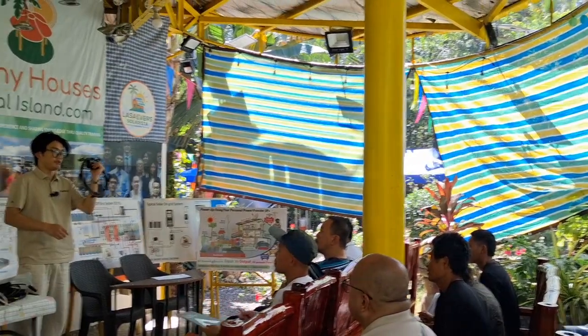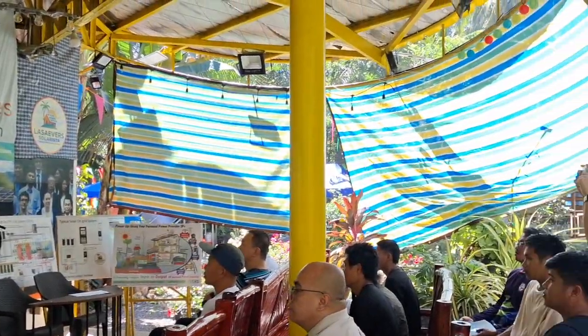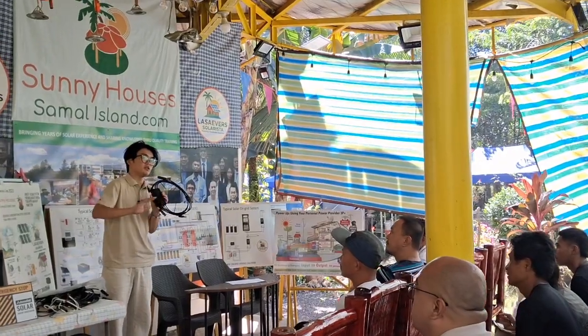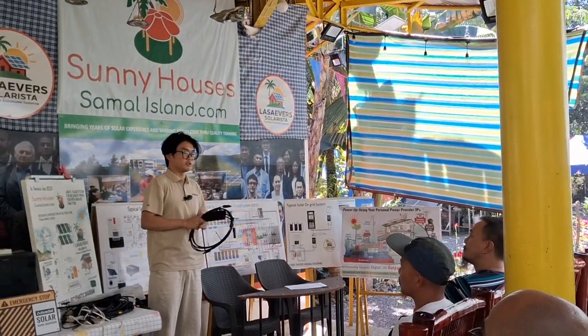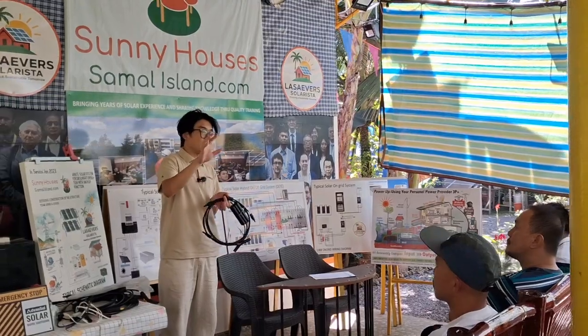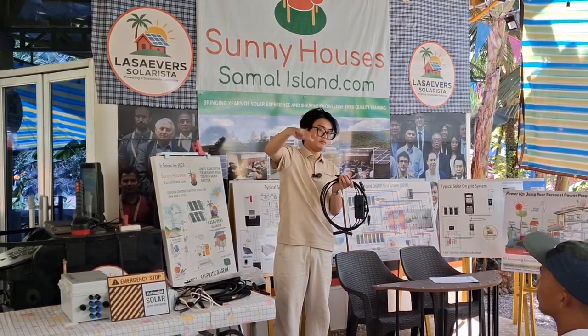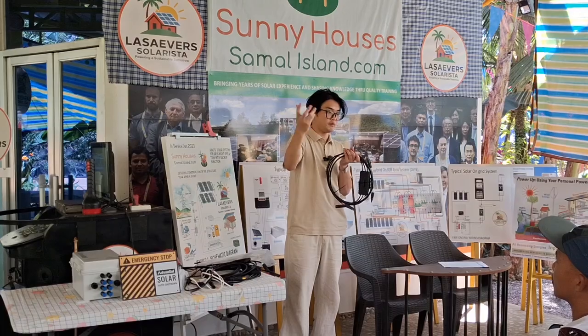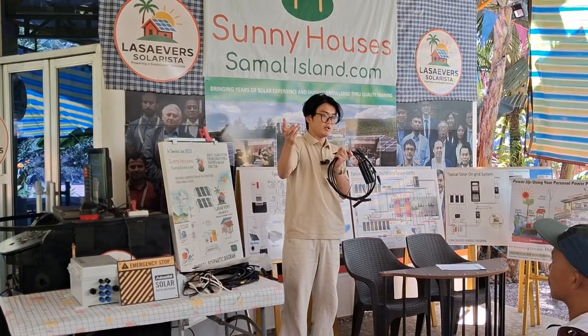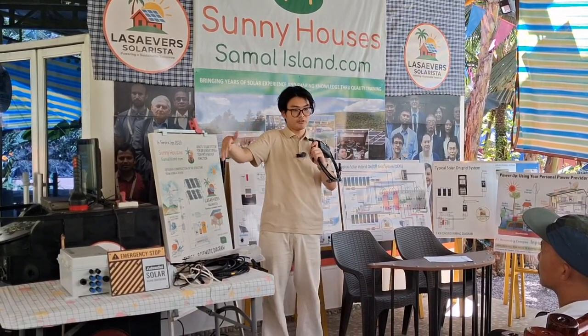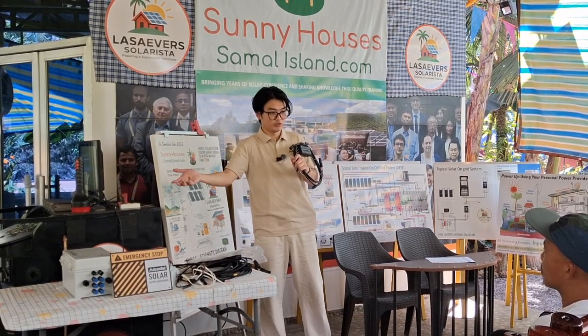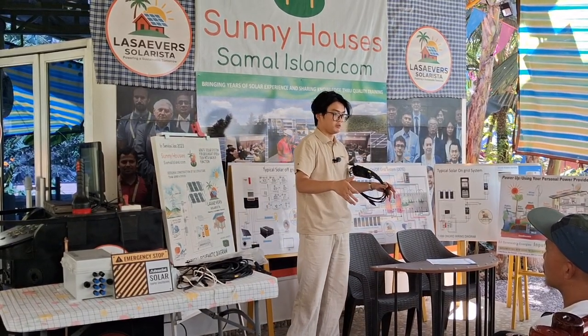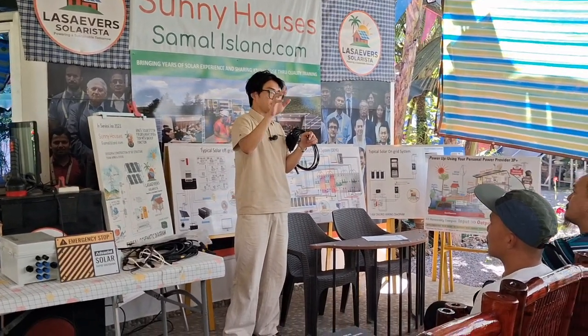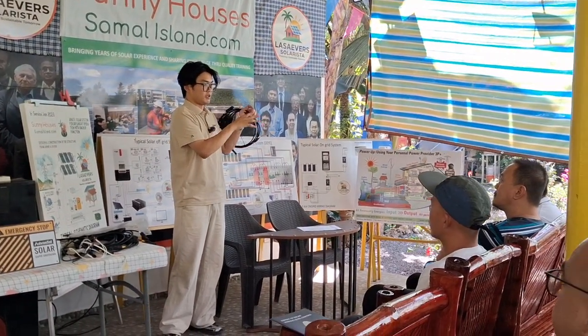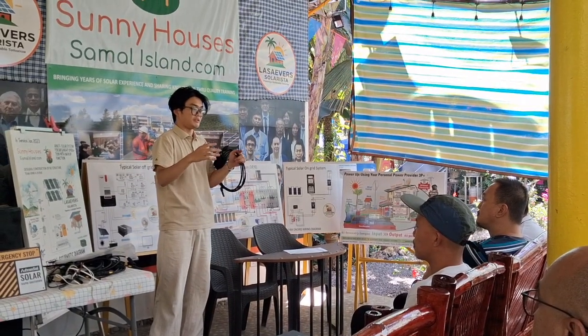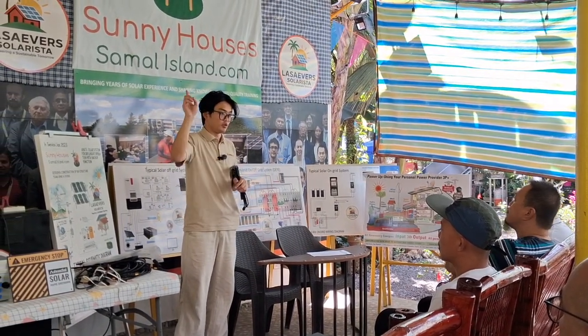It's to ensure the safety of the PV system, because without these kinds of devices in a normal rooftop solar system, as long as there is sunlight on the PV panel, there will always be power output. The inverter can shut down the AC high voltage, but it cannot shut down the DC high voltage. So in the daytime, as long as there is sunshine, there will always be high DC voltage in the PV array, in your rooftop area.